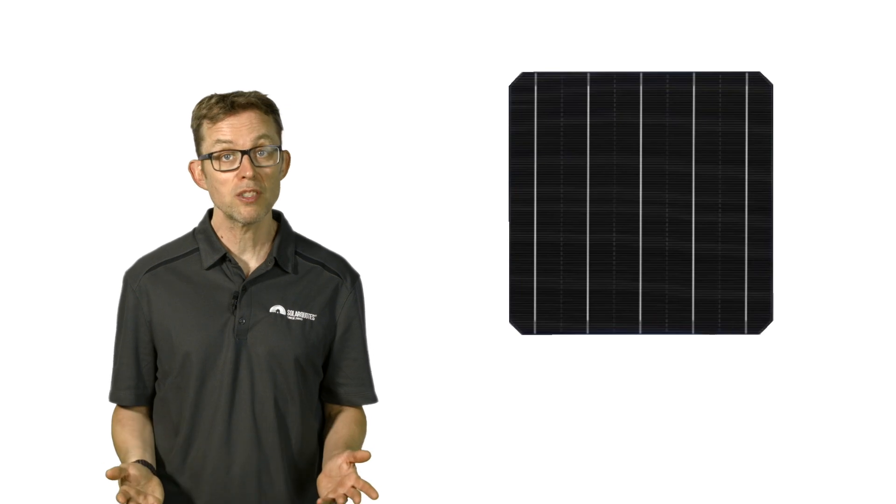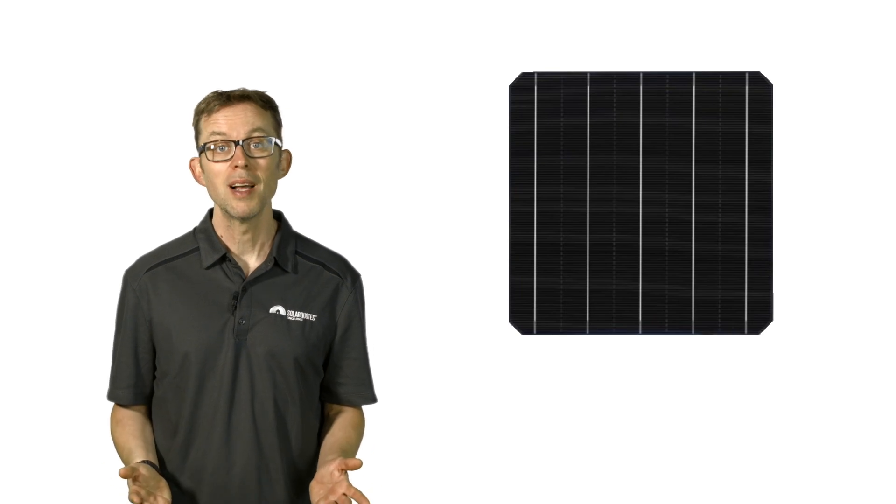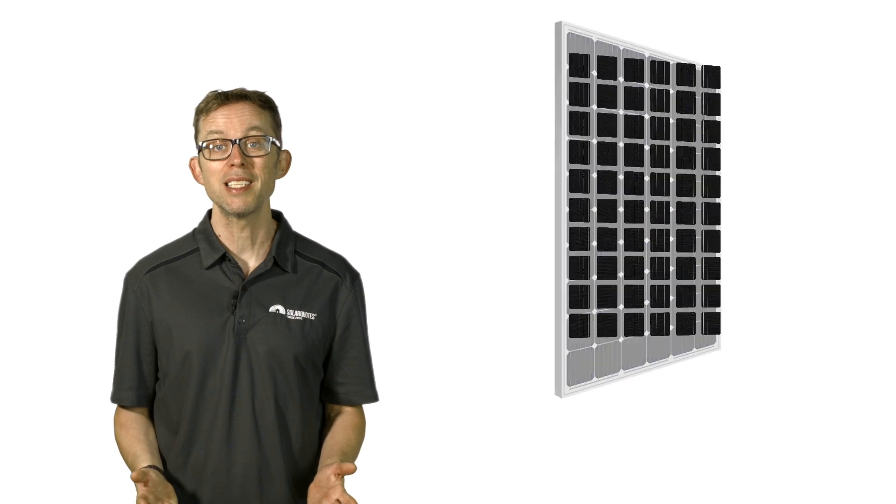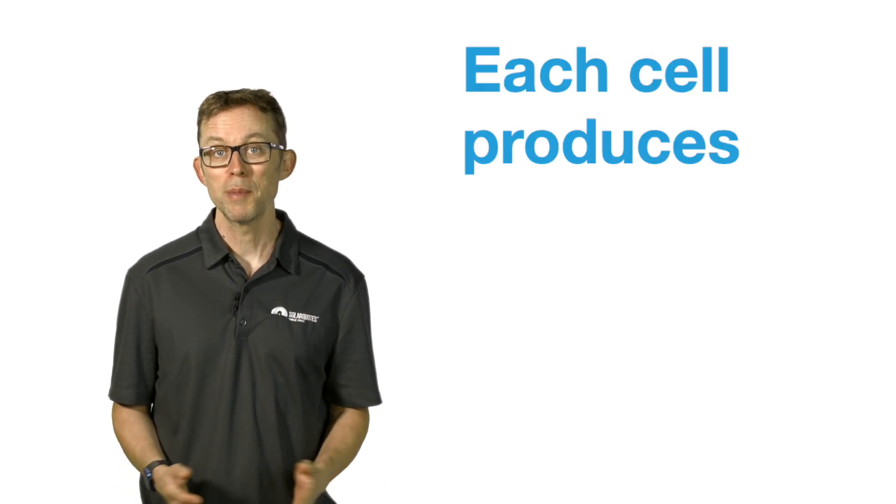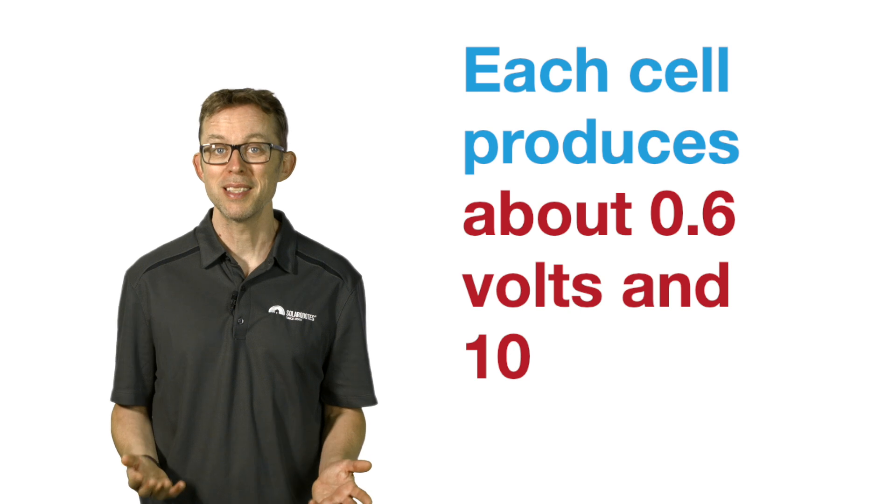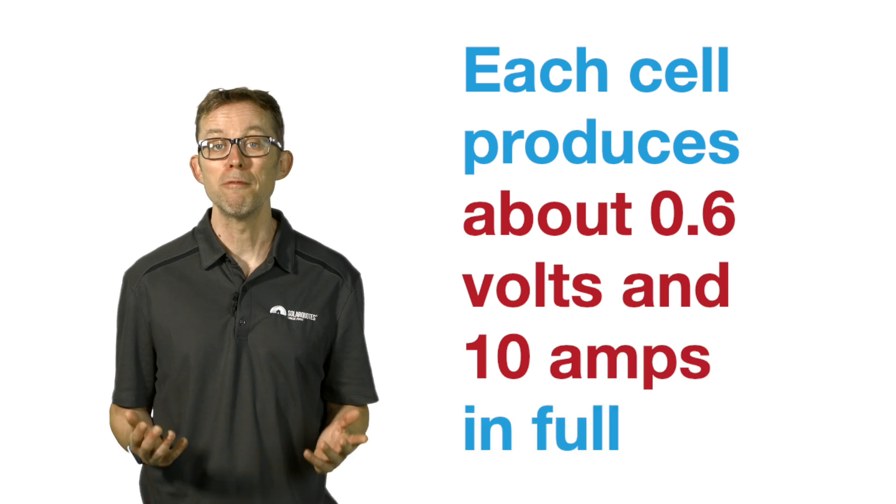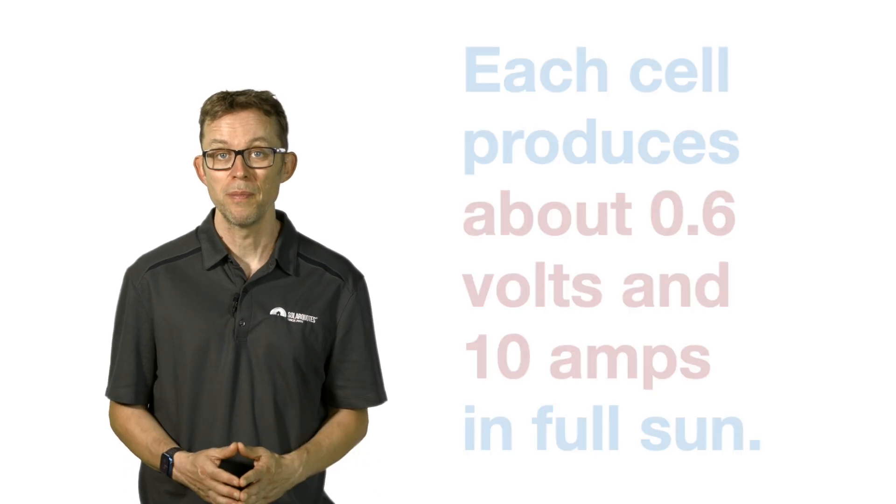A residential solar panel has around 60 cells that are roughly six watts each, arranged in a six-by-ten matrix. Each cell produces about 0.6 volts and 10 amps in full sun. The cells are electrically connected in series, so if one cell becomes shaded it restricts the current to every other cell in that string. That's why you need to keep panels clean.